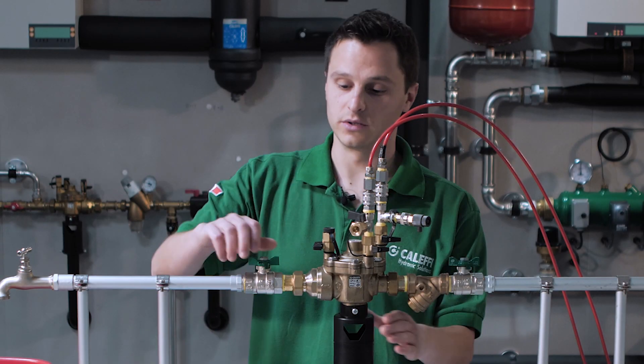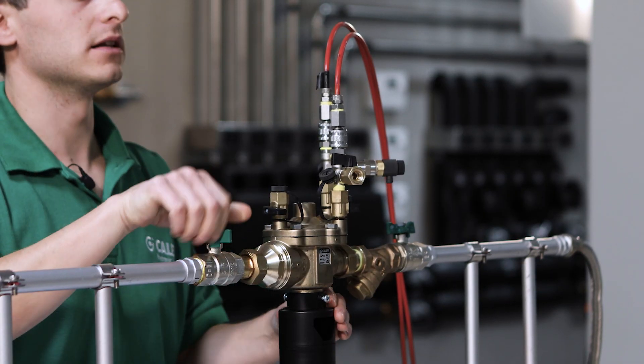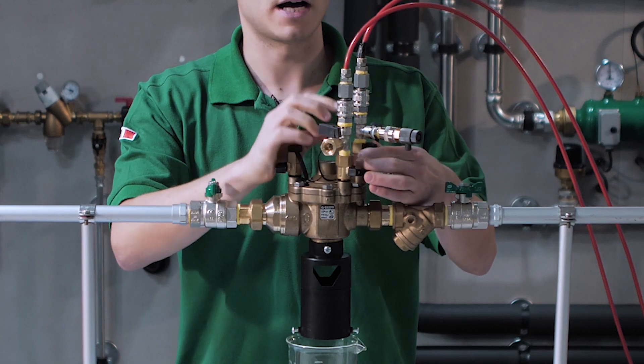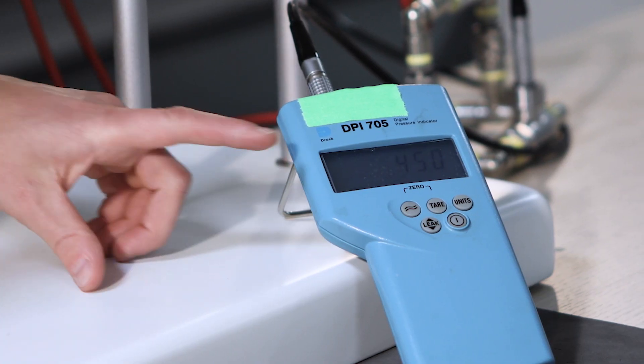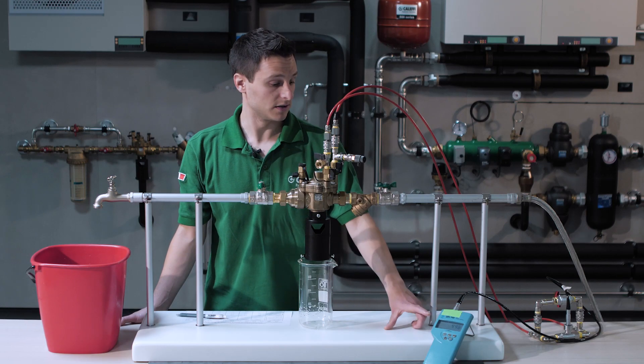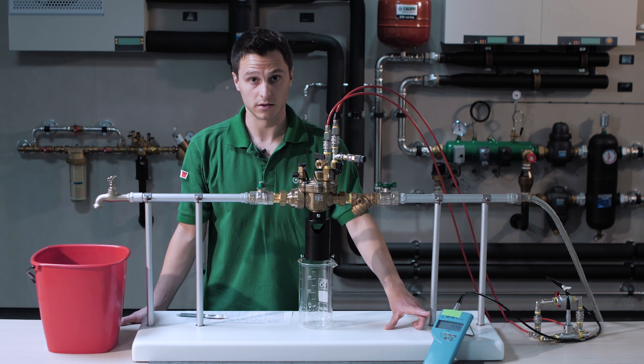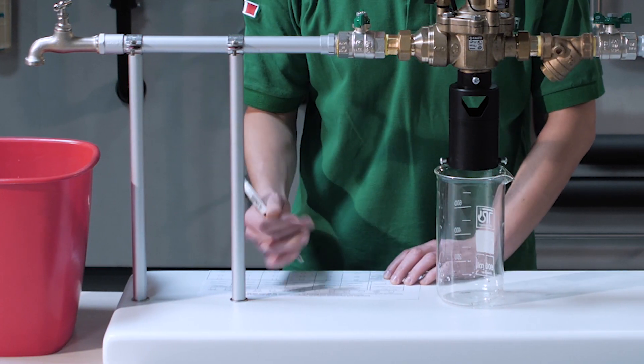As the first check, with the downstream shutoff valve closed, verify that the differential pressure between the upstream test port and intermediate chamber test port is at least 340 millibar. In our situation, the value is greater than 340 millibar, so we can note this on the inspection and maintenance protocol.